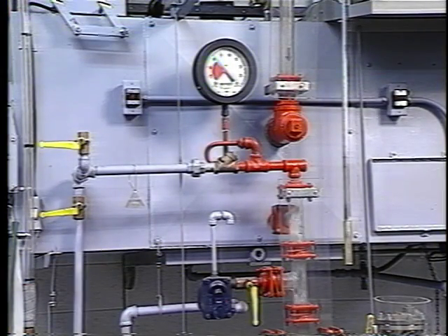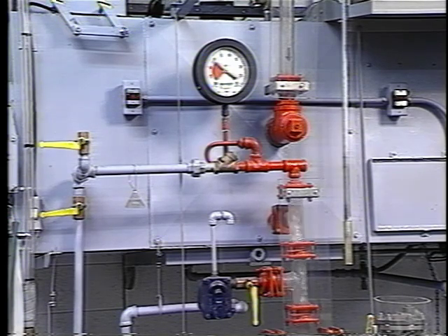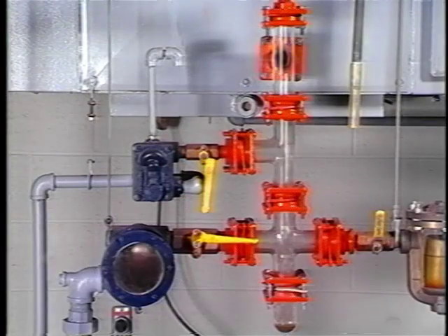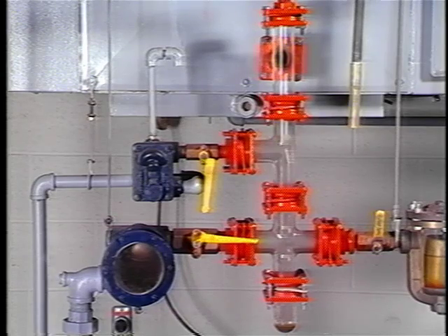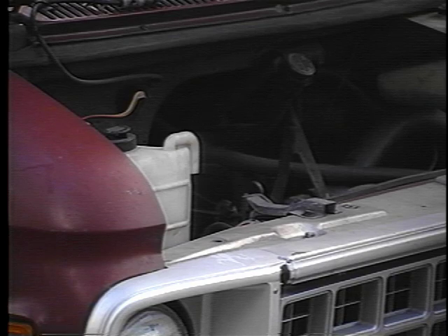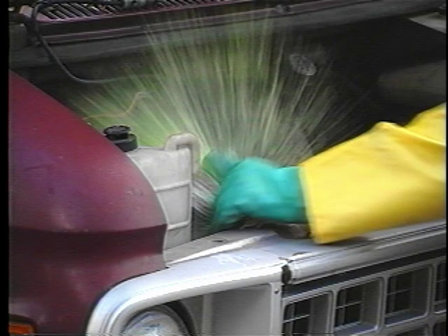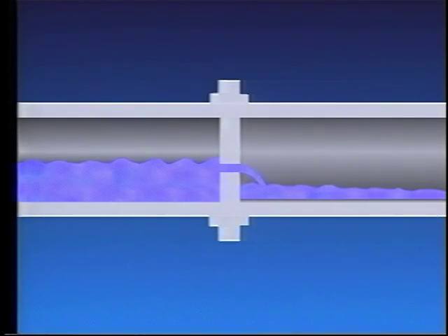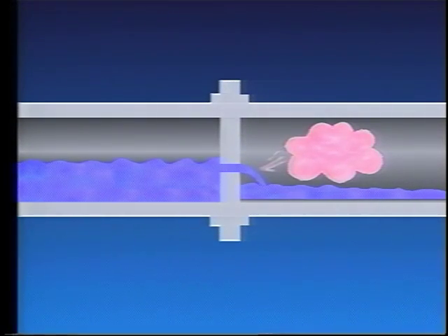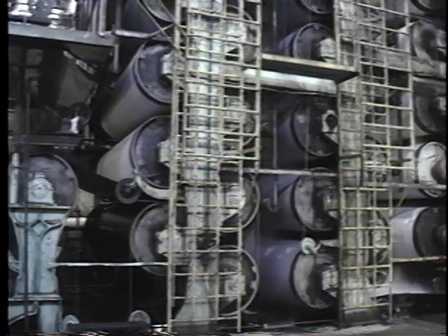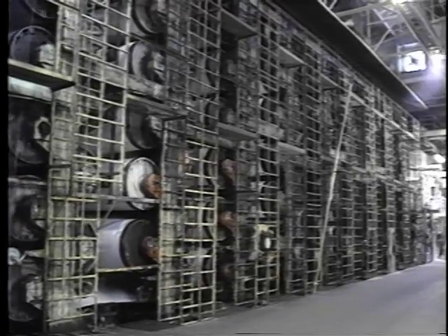The condensate impacts at the center of the void and transmits shock waves to any surrounding components. On a larger scale, the same phenomenon can occur much more slowly. If steam condenses faster than it can be replaced by the boiler, the pressure in a closed system will drop slowly. If the situation persists, the pressure will fall below atmospheric, forming a vacuum, which will impede normal flow inside a steam system. Opening the radiator cap on a hot automobile can be very dangerous because the pressurized coolant may be hotter than its boiling point at atmospheric pressure. In a steam system, flash steam occurs when sufficiently hot condensate is released into a lower pressure line. While some systems are designed to use flash steam for lower pressure service, its occurrence can impede efficient system operation.